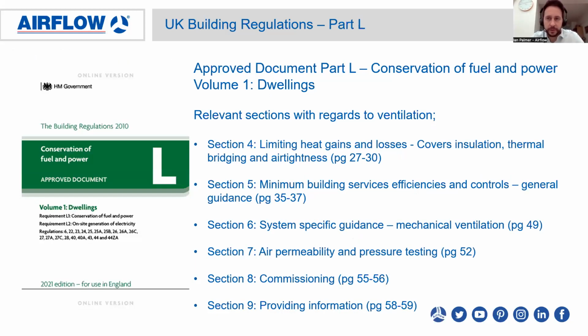Moving on to Part L, the conservation of fuel and power. The relevant sections here with regards to ventilation are section 4, which covers limiting heat gains and losses, insulation, thermal bridging and air tightness. Section 5, which is minimum building services efficiencies and controls, general guidance. Section 6, which is system specific guidance on mechanical ventilation. Section 7, which is air permeability and pressure testing. Section 8 on commissioning, and Section 9 providing information.